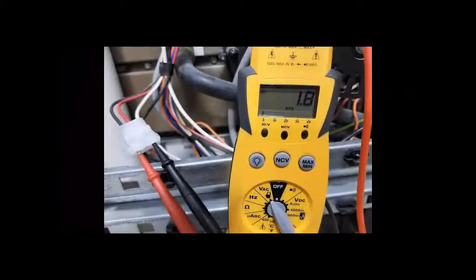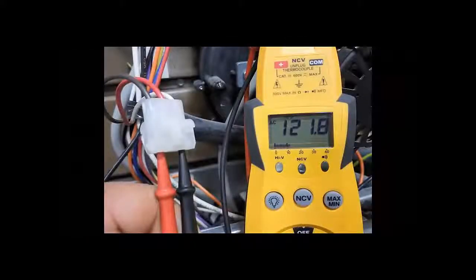Now connect your voltmeter leads to the wires running back to the circuit board and turn the main power back on. Note, the thermostat must be calling for heat in order for this test to work. You should get a reading of 110 to 120 volts plus or minus 5%. If you don't get a correct voltage reading, you either have a bad circuit board, a mainline voltage problem, or defective wiring between the circuit board and the inducer motor. If you are getting correct voltage to the inducer motor and it is not running, then the motor itself is probably bad. There are a lot of things that can cause an inducer motor not to operate. One basic thing you can easily check for is the condition of the motor windings, which we will do in the next video. But right now, let's take a minute and watch a quick video on how to check for mainline power to the inducer motor.